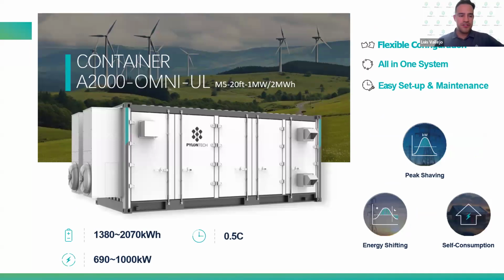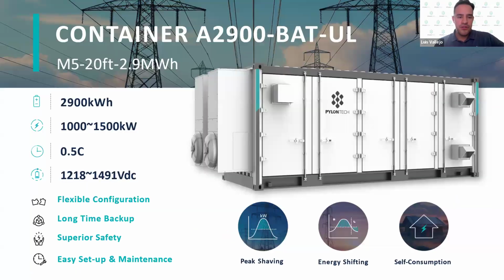So for our container solutions, we have 2, both of them 20-foot container solutions. This is our first one, which has a capacity of 1.3 megawatt hours all the way up to 2 megawatt hours. And this one is paired with Sinexcel inverters, half C systems. And this is mainly used for peak shaving, energy shifting, and self-consumption. This is the bigger brother, which has a capacity of 3 megawatt hours, also half C rated, and the PCS ranges from 1,000 kilowatts all the way to 1,500 kilowatts.